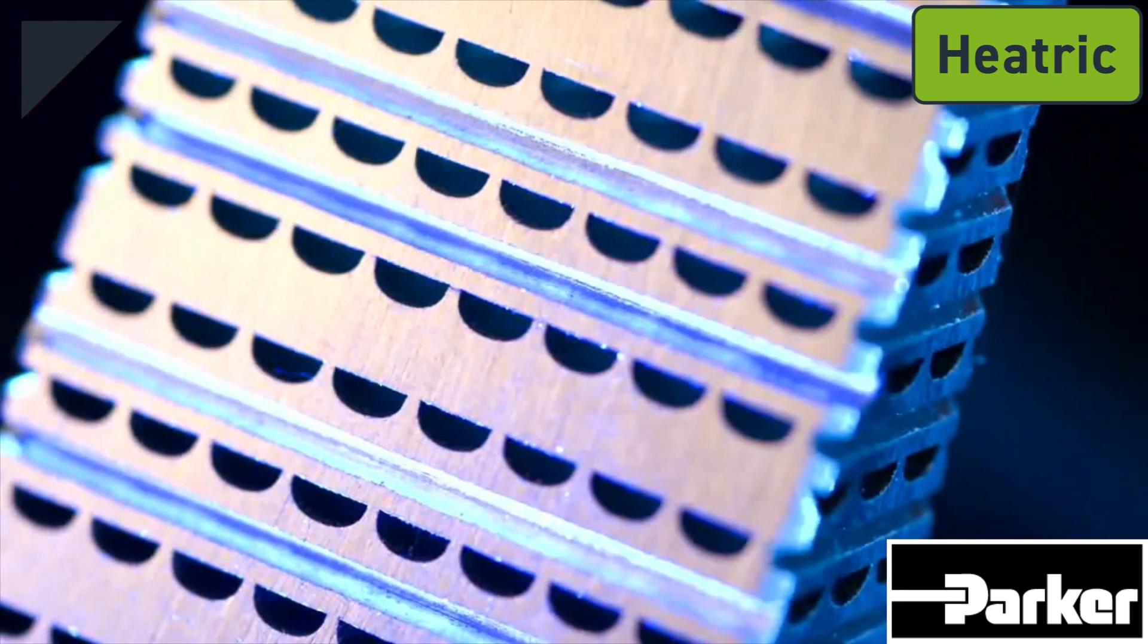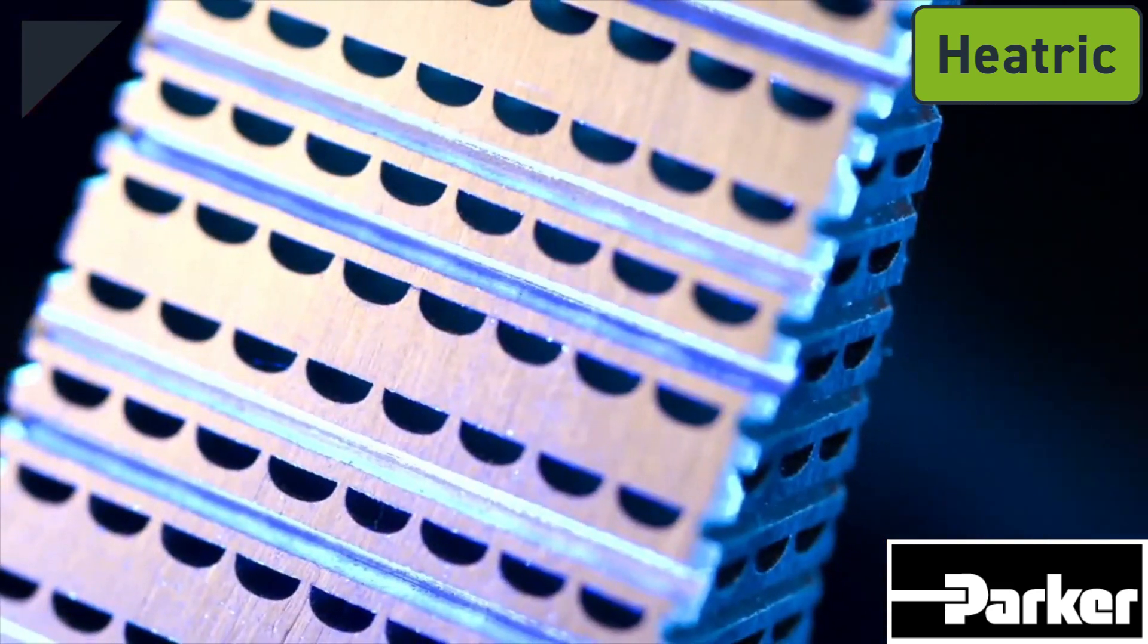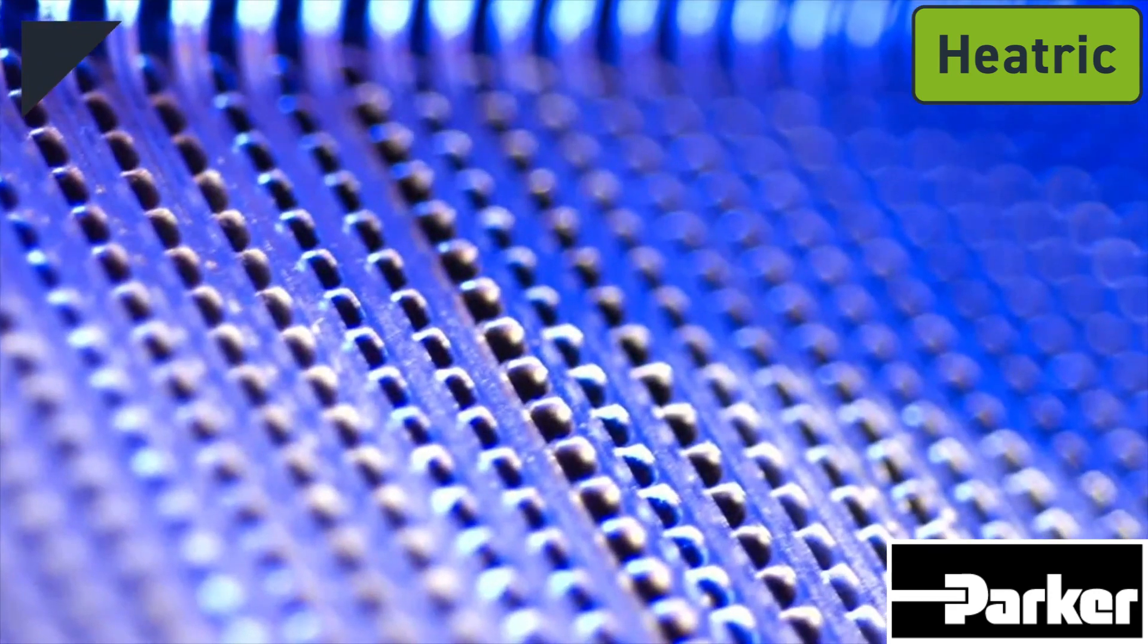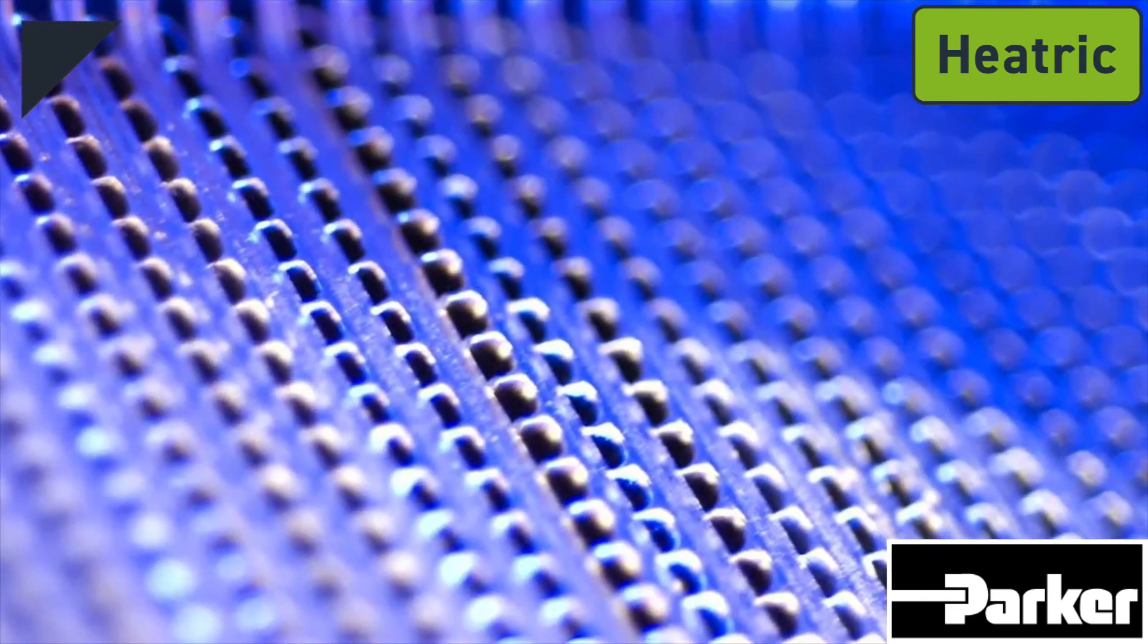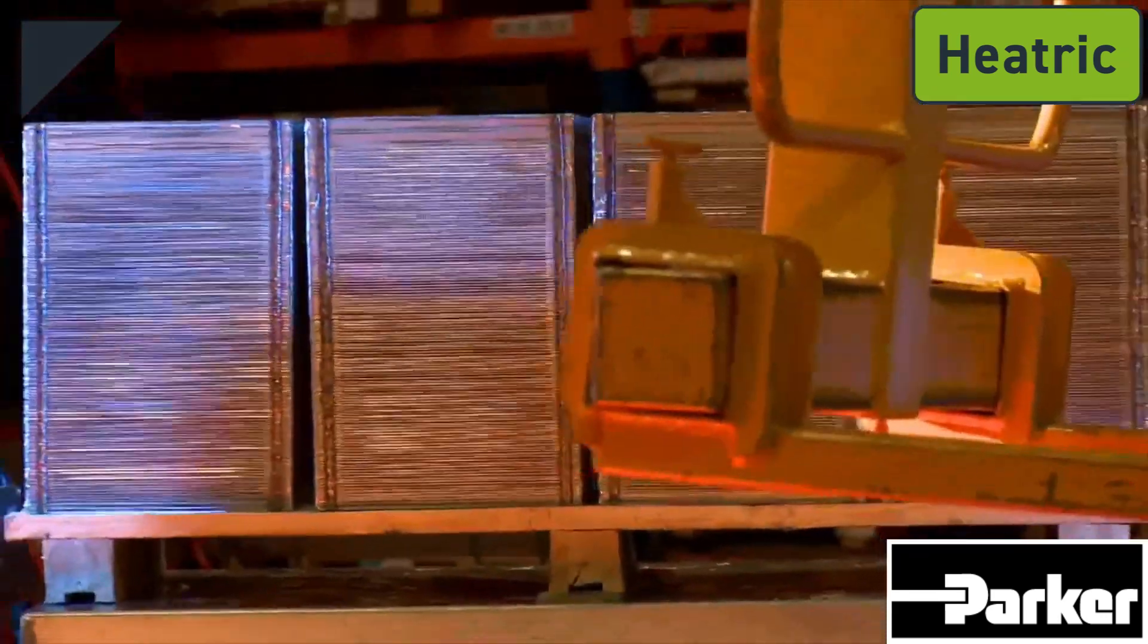The diffusion bonding process does not employ any braze, flux or gaskets in the construction of the heat exchanger core. This bonded core behaves as a single metal block with engineered holes running through it. It can then be machined and welded using conventional fabrication techniques.